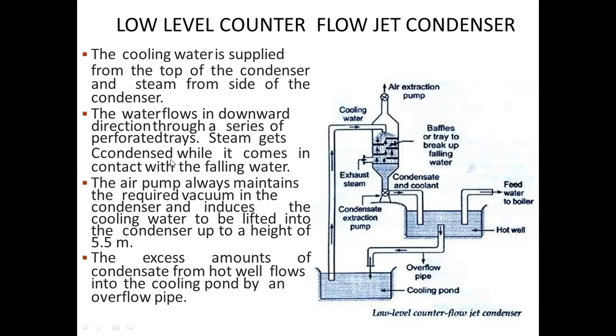Steam gets condensed while it comes in contact with the falling water. The air pump always maintains the required vacuum in the condenser and induces the cooling water to be lifted into the condenser up to a height of 5.5 meter. The excess amount of condensate from the hot well flows into the cooling pond by an overflow pipe. You can see this here.